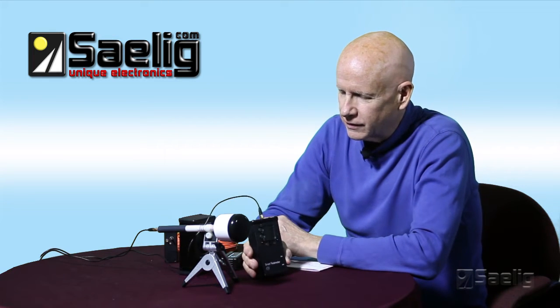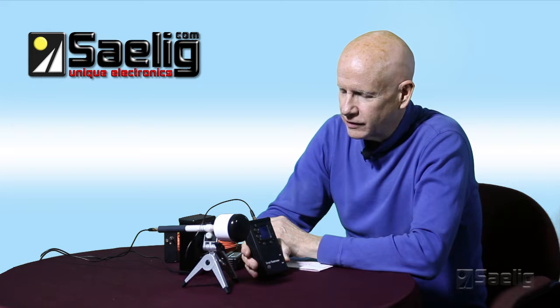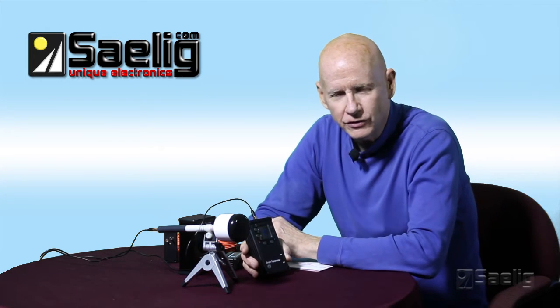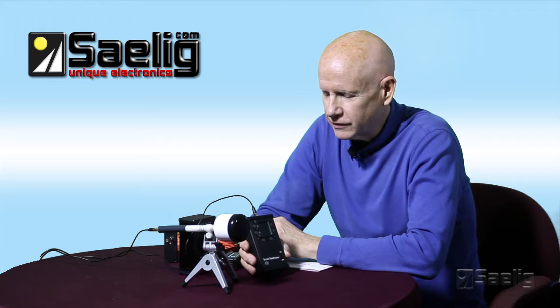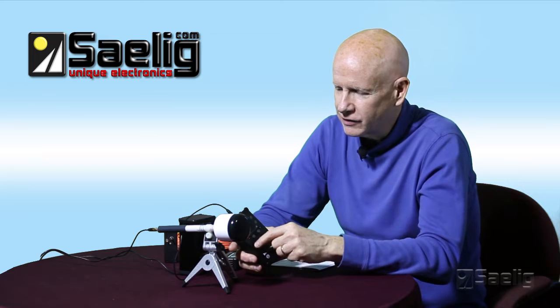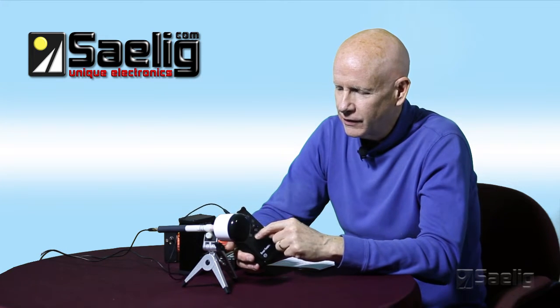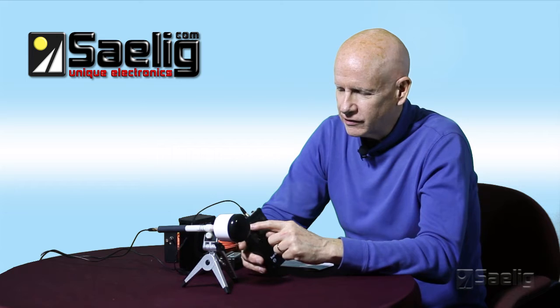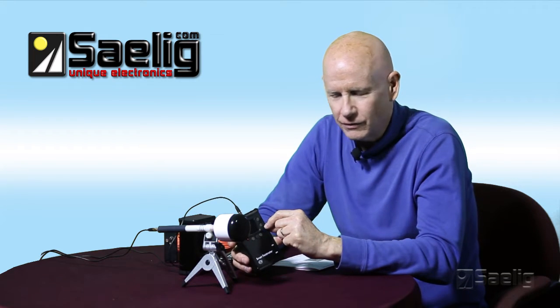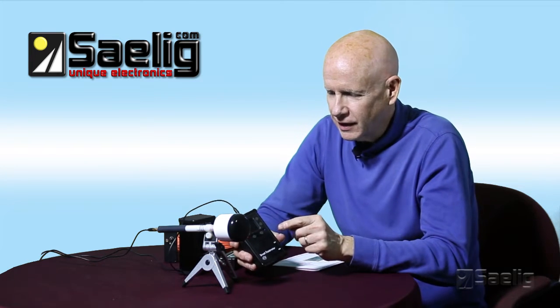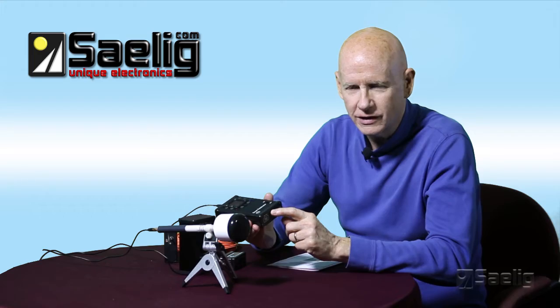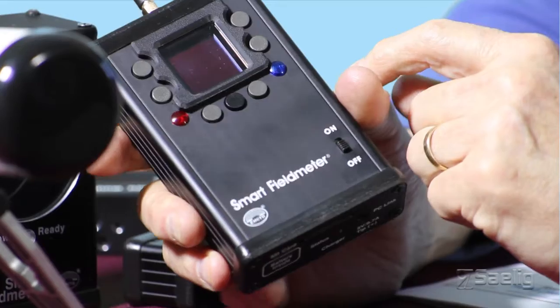So we'll talk about the meter for a little bit here. As I mentioned, it's an auto-ranging meter that has the ability to store calibration constants and linearization curves in it for 4 different transducers. It has a color display up here that's menu driven, and you use these soft keys around it to pick what selections you want. The information about the calibration constants is contained on this SD card in here, so it's easy to return this for calibration and just have the card updated, put it in here, and you're all set to go, like that.